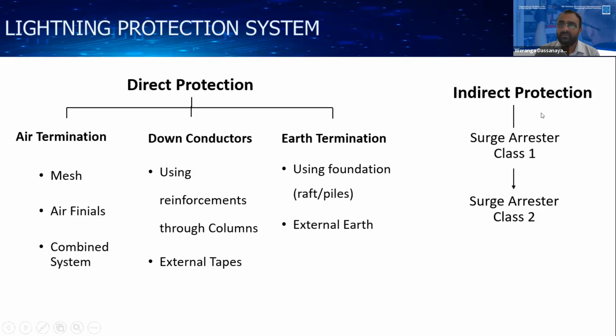So indirect protection means you have to stop the current coming into the building from the transmission line or the distribution line. For that, you are using surge arresters. There are two types of arresters. One is class 1 and the other is class 2. And there is another type available, class 3, mostly used with very sensitive equipment. And today in the market there are surge arresters available as class 1 plus 2 also. So that's a combination of class 1 and class 2.